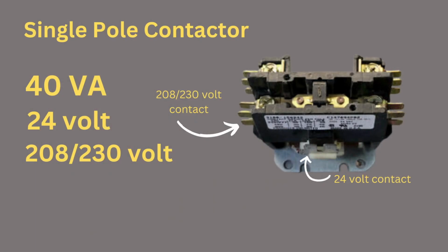A single pole for a residential home is 40 VA, 24 volt, 208, 230. So, like I said, the little single connections on each side of the contactor are what feed your 24 volt in from the home. And then the main voltage comes in from one side and feeds in, and all the parts on your condensing unit, your fan, compressor, all connect to that side, and the lead that feeds over to your capacitor. So it all feeds those as well.